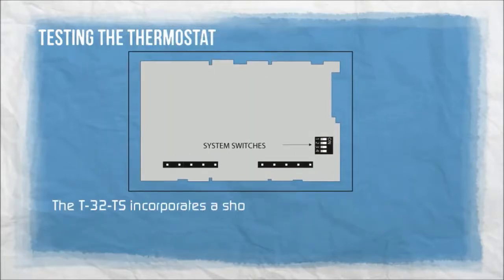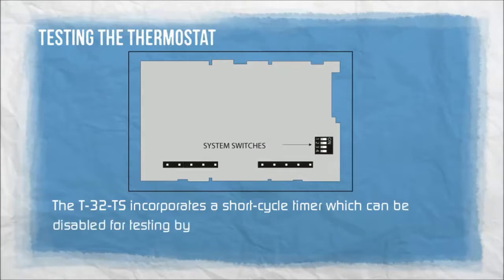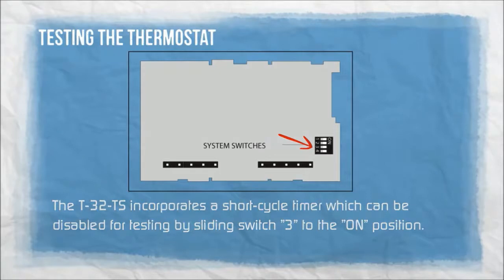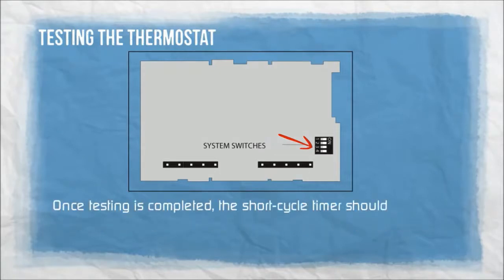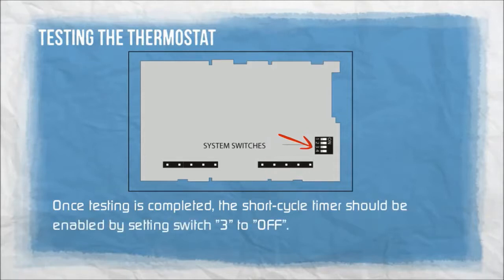The T32TS incorporates a short cycle timer which can be disabled for testing by sliding switch 3 to the ON position. Once testing is completed, the short cycle timer should be enabled by setting switch 3 to OFF.